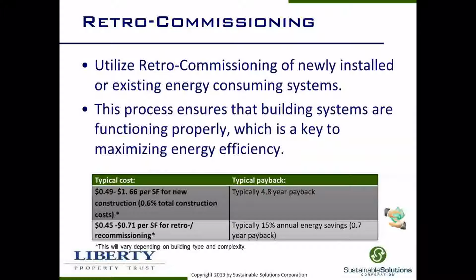But for all of us on the phone talking about existing buildings, retro-commissioning is really effective, where you come into an existing building and basically monitor and evaluate the operation of the various equipment. We just recently worked on a project, actually a Liberty building, and the retro-commissioning was conducted, with about a 5 to 10% savings in energy achieved just by improving performance. That was in an office building. However, even in a warehouse building, you'll have various HVAC units, office areas, things like that should be evaluated. So there is good benefit to that.